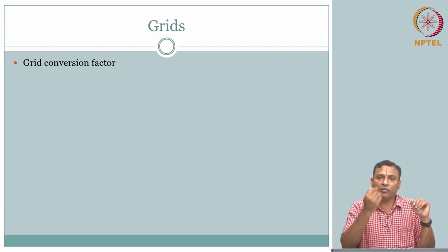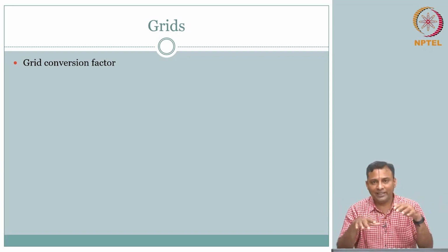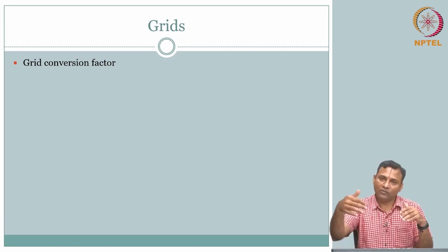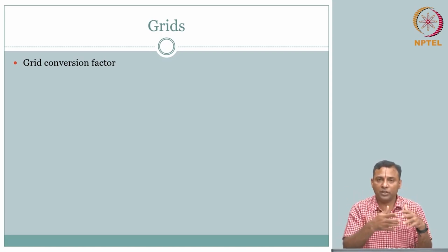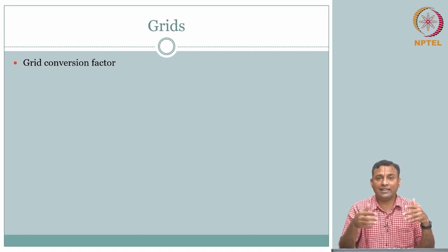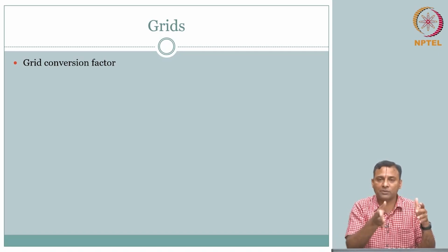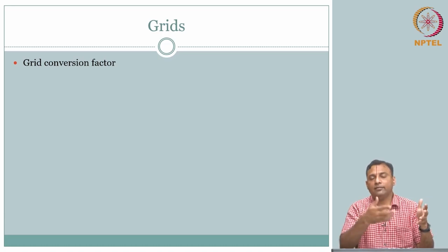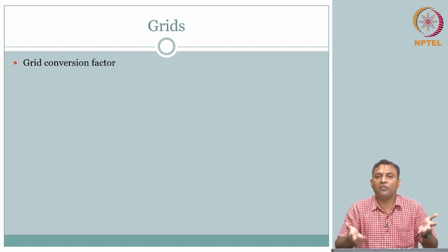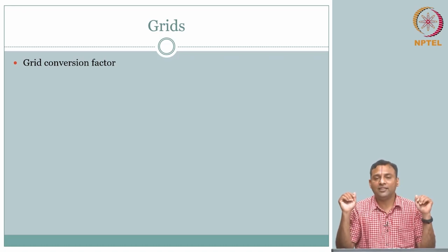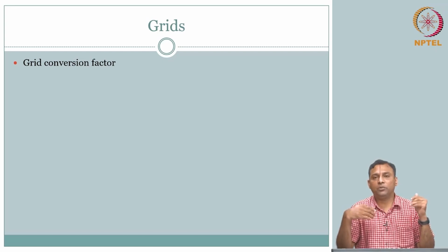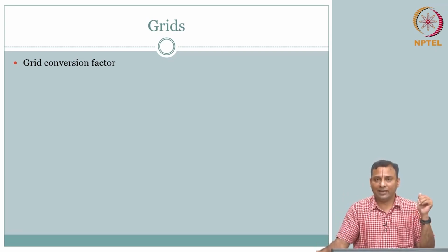If you increase the number of photons for the same schematic, then whatever is Compton scattered will reduce because of the grid. Whatever signal is lost due to the grid placement itself, you get more photons coming through because you have increased the absolute number of photons. That means your exposure is increased. So, there is always a trade-off. Your exposure is increased, but you get better signal to noise ratio because the grids have reduced the scattering.